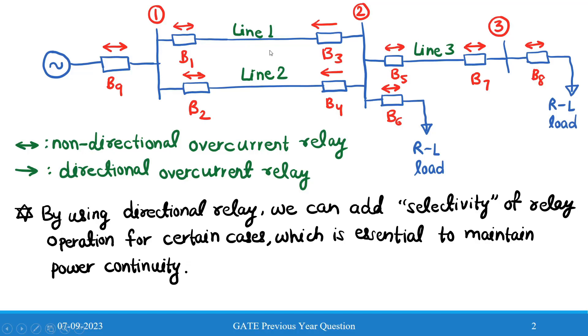We can understand this from a simple example. Suppose a fault occurs at line one — then circuit breaker three will see the opposite current, so relay R3 will operate. Relay R4 will not operate, so power in the rest of the lines will remain as it is, and line one will be isolated.